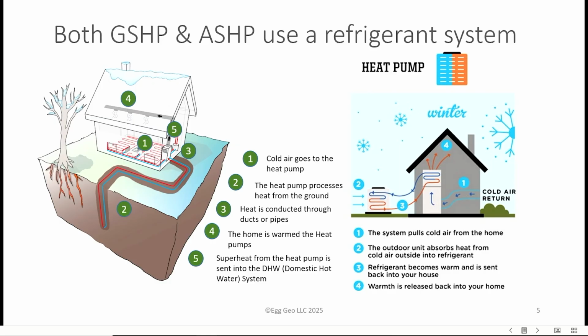Now, the reason a geothermal unit can operate more efficiently is that it's not subjected to the outside air temperatures. The outside air temperatures here, while they might drop well below freezing in the winter, down here in New York, the temperature at 6 feet or below is 55 degrees year-round. So you can extract energy from that ground source year-round, at a high COP. 55 degrees will give a heat pump a COP of about 4.0 to 1. In other words, a 4 COP.